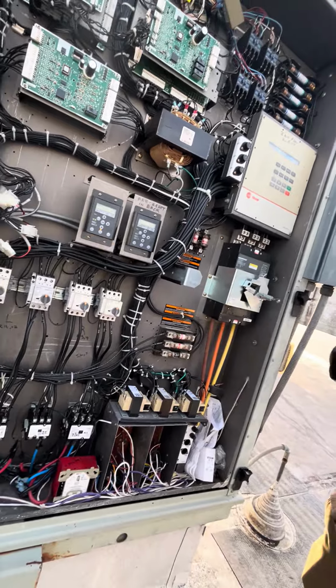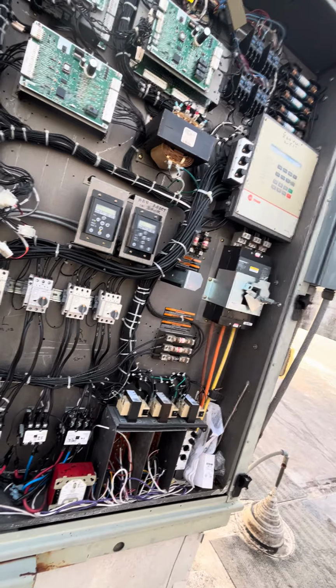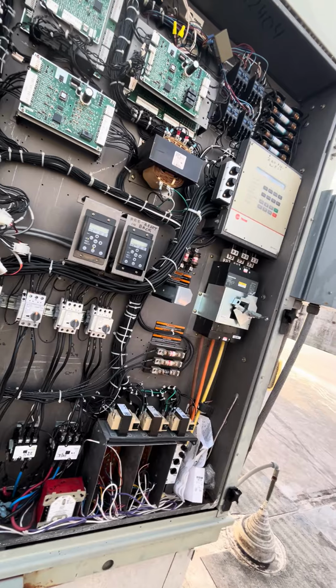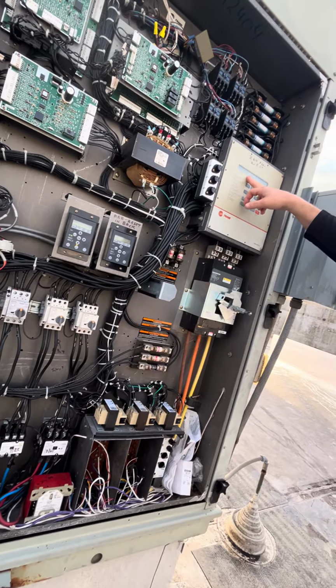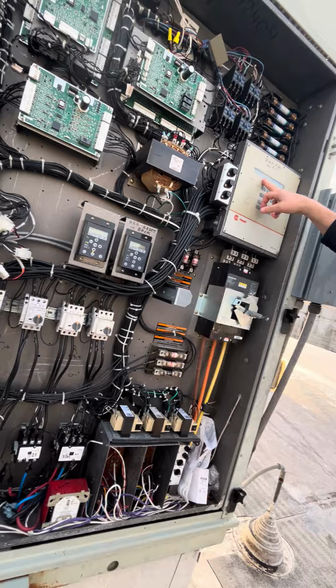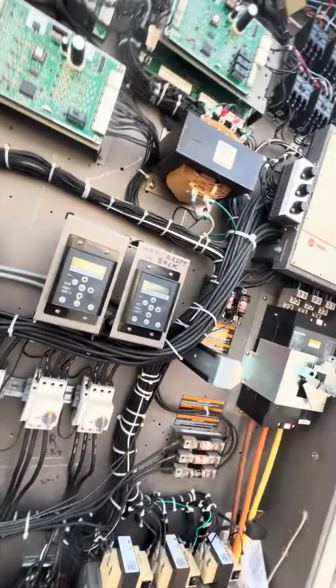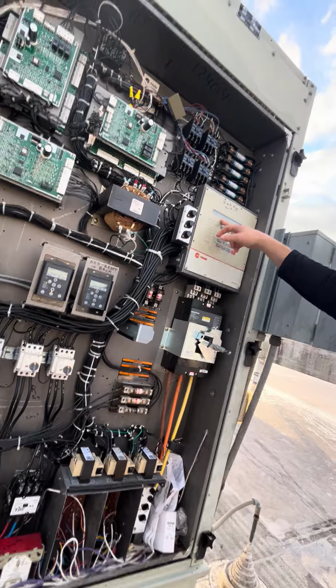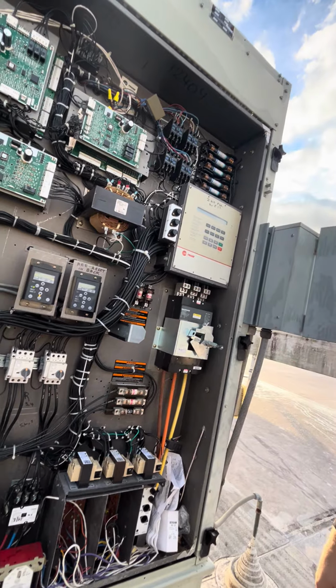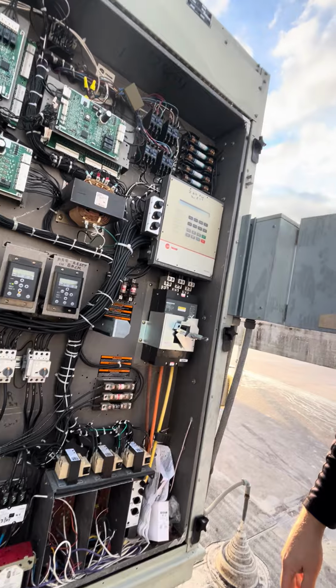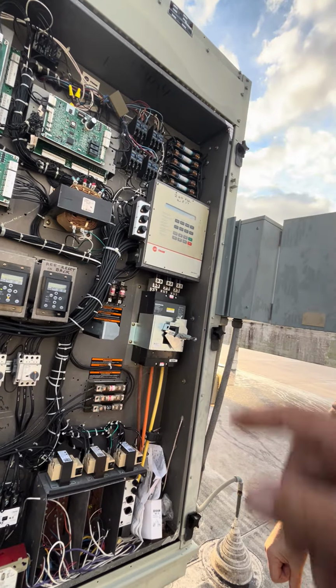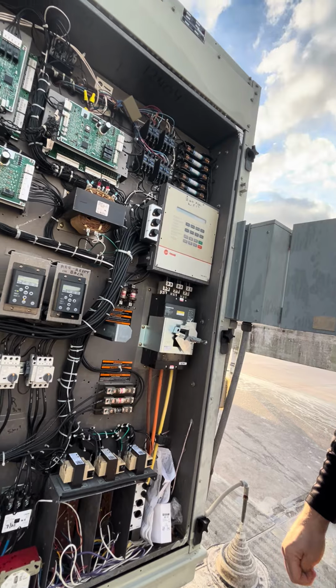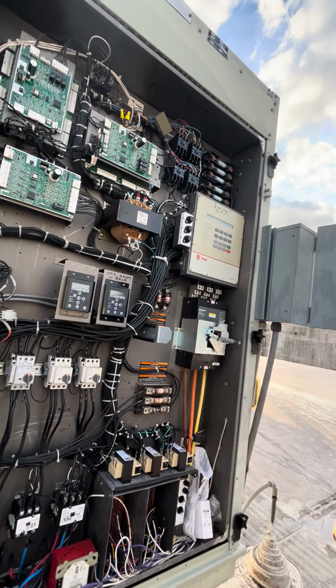99% of our units across the entire country are the 0 to 5 volt, and that's still what we were buying. But you're saying this is set up for zero? It's not set up. That's what it comes from the factory. Okay. So I want to make sure that somebody didn't do something that doesn't match the G-Bass. It's a checkbox on the order form. Okay. They ordered this one as a 0 to 10. But you would need to make sure that when you order a G-Bass, that you're getting it for what you're setting up here. Correct. Yes, correct.